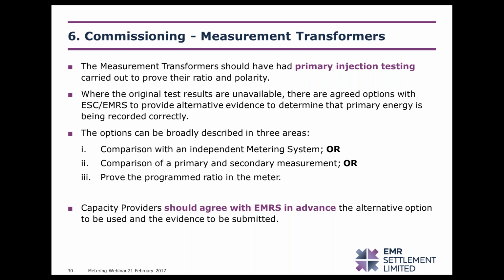However, please be aware that should the ratios in the measurement transformers be multi-ratio types, so that is where you have a choice of two CT ratios perhaps, so maybe a 400, 200 to 1 amp CT, we must provide evidence to demonstrate what ratio the meter has been connected to. Site acceptance tests can often inject both ratios and not give a clear indication of what winding has been used when it was finally connected to the meters.